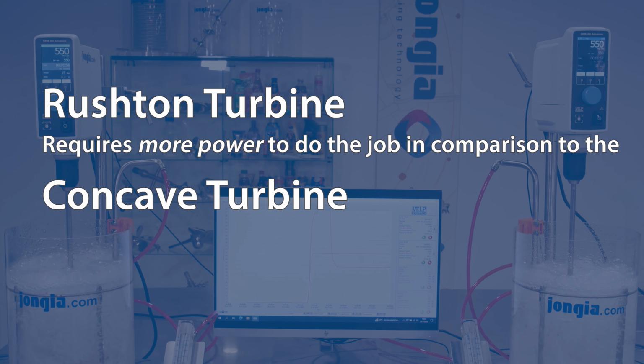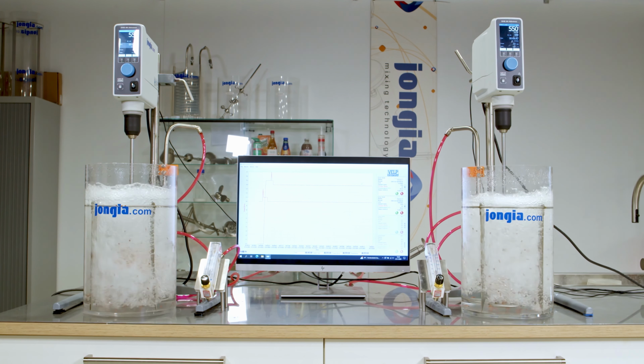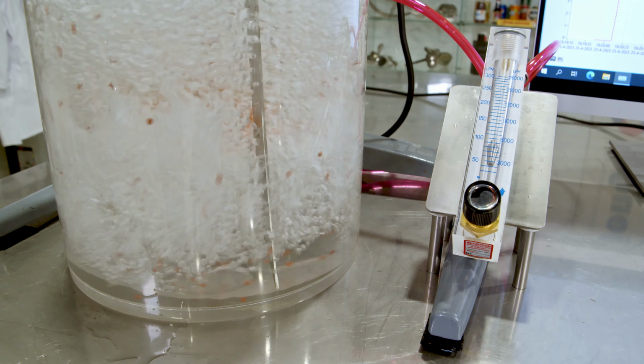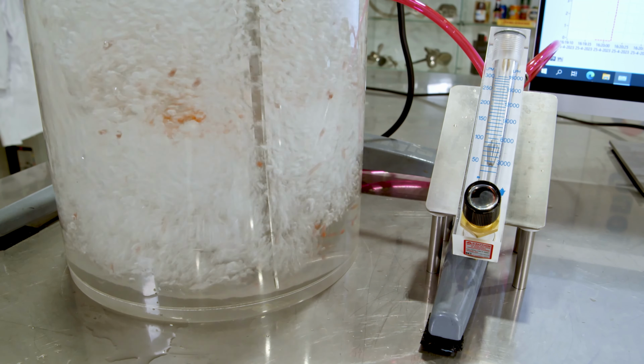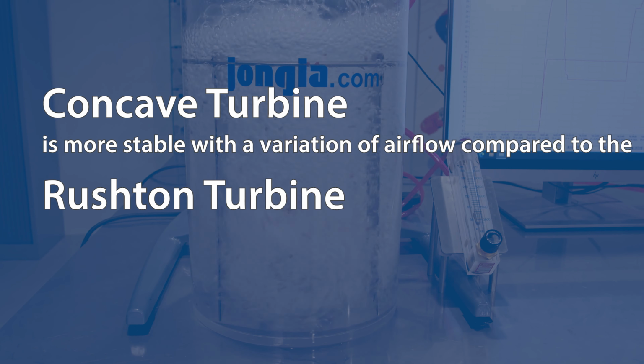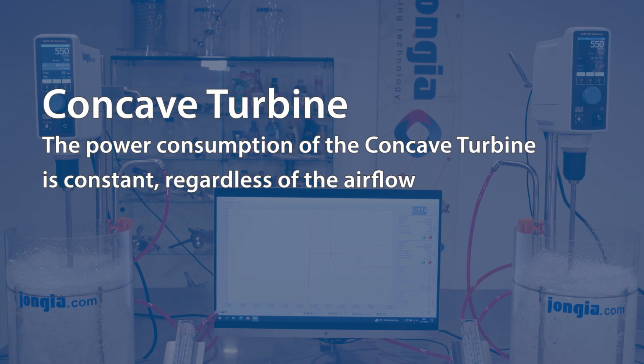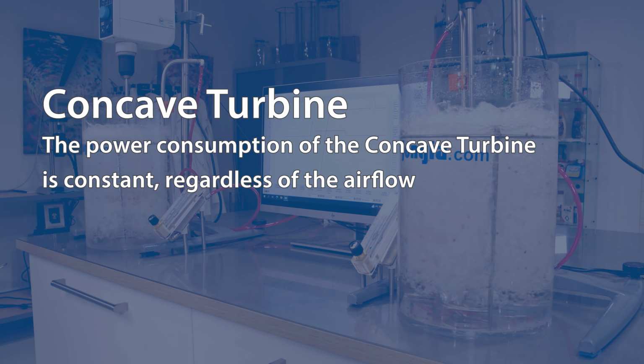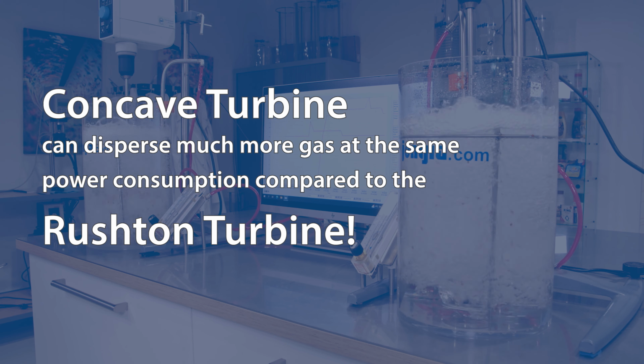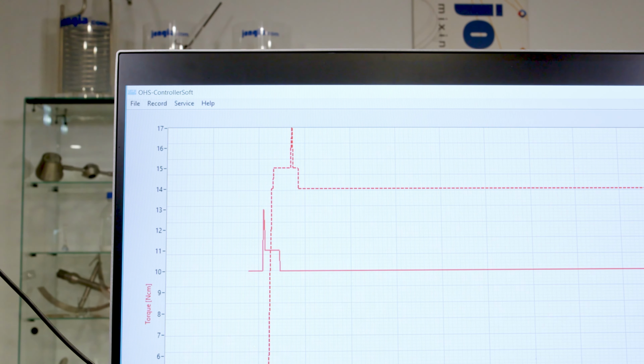You can clearly see that the concave turbine hardly has any difference in Newton centimeters compared to the Rushton turbine. Also, the concave turbine is much more stable with variation of airflow and the power consumption is constant regardless of the airflow. In other words, the concave turbine can disperse much more gas at the same power consumption compared to the Rushton turbine. That is another quite interesting aspect.